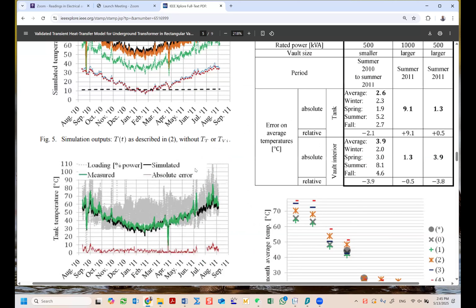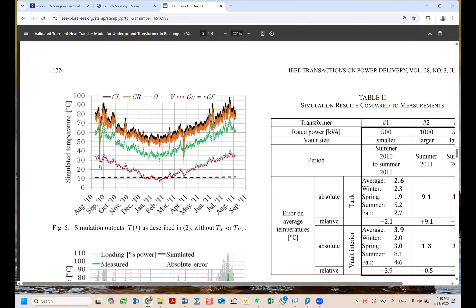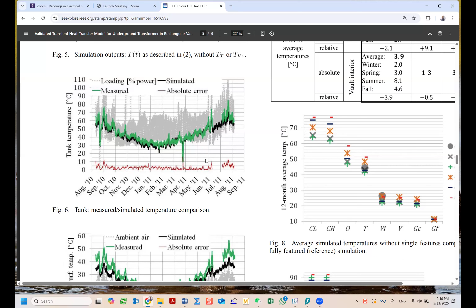So it's over 1 year. As you can see, the times when this transformer was disconnected, the temperature drops. These are simulations, and the others are measurements. Measured versus simulated. We have the loading, we have the measurements, and the absolute error is never more than 10%. There's a region between June and July 2011 where there was no information because the device stopped reporting the measurements, but it captured things again very nicely.